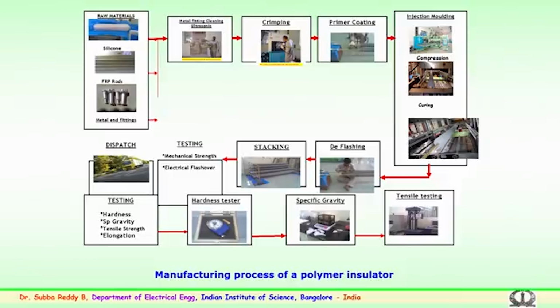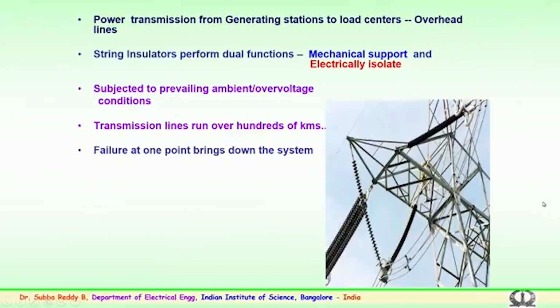So, this is how the technology has improved, and these are the recent insulators, or of recent origin, which are organic in nature and are being used for the EHV and UHV transmission systems. So, we have looked into the different types of insulators which have been used over a period of time, and we know that power transmission from the generating station to the load centers is by overhead transmission lines. So, as mentioned earlier, the string insulators which are shown here perform dual functions.